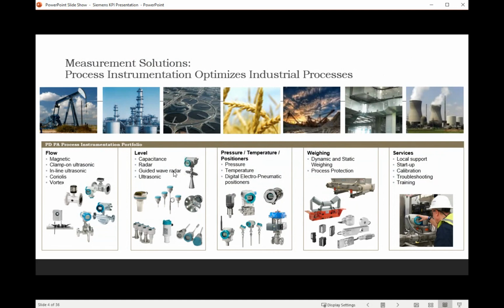So looping back to the second to the left, which is level, and the reason why I say that for the end is because that's really going to be our topic today. And level really falls into either a contacting or a non-contacting type of technology. So a contacting technology would be something like a guided wave radar or a capacitance, where you actually have a rod or a cable or something that's touching the process. Non-contacting, there's really 2 flavors of that ice cream, where you're going to have an electromagnetic radar or an acoustical, which is an ultrasonic type of signal. Both of those are very similar insofar as they're going to send out some sort of a pulse, and they're going to listen for an echo, and it's basically time of flight. And I know Josh is talking about that, I think, in the next slide.